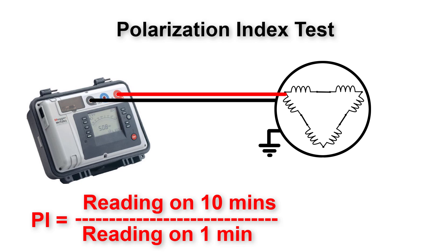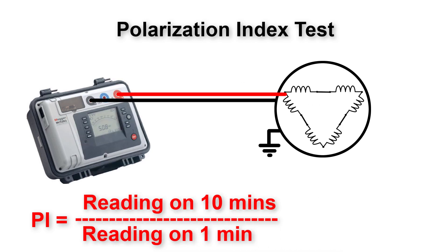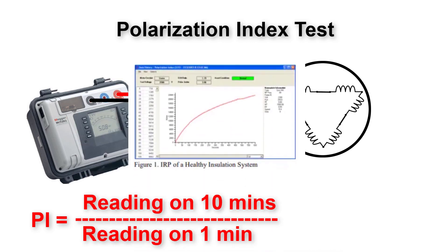This ratio is then compared to a standard table. If the ratio is below 1, this is dangerous and means the insulation is degrading over time. Between 1 and 1.4 the condition is poor; between 1.5 and 1.9 it is questionable; between 2 and 2.9 it is fair; between 3 and 4 it is good; and above 4 it is excellent.